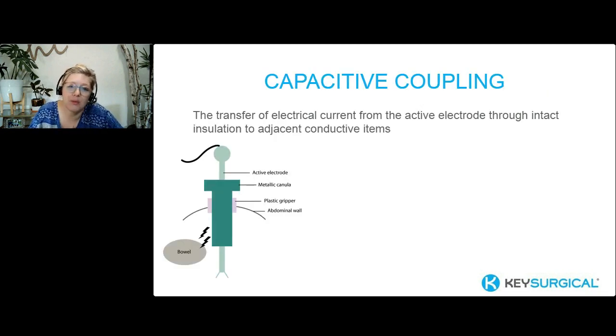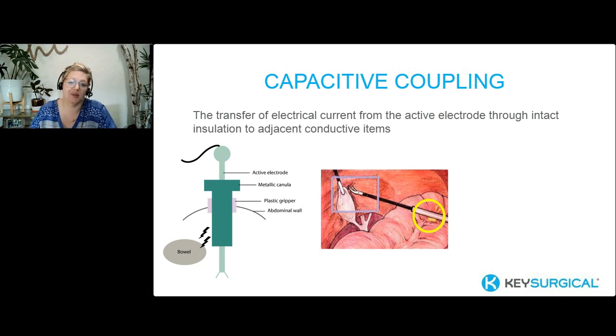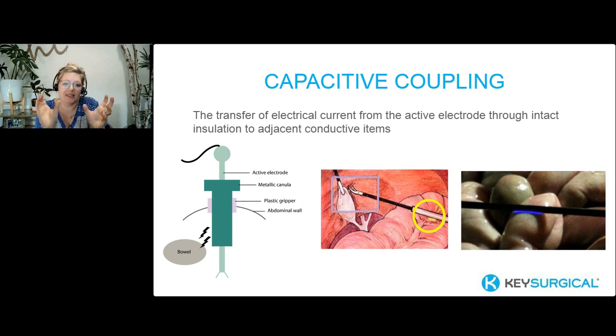So the next type of coupling that we have, and coupling, there's two things coming together, is capacitive coupling. So that's the transfer of electrical current from the active electrode through the intact insulation to adjacent or conductive materials. So we see this a lot when we have a metal cannula, a plastic gripper, when we kind of mix media in different ways. And what can happen is then that becomes energized, that's now conducting electrical current. And as you can see, I think that middle picture is really the best. You don't realize that it's now conducting energy, and it's being applied to a tissue where you did not want an effect, especially in abdominal procedures. Of course, we see this happen in the bowel.